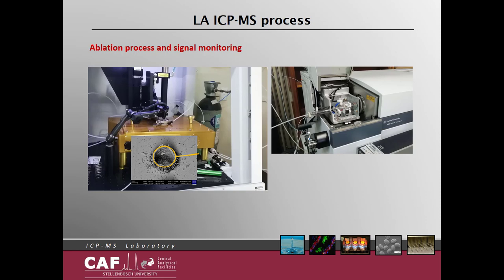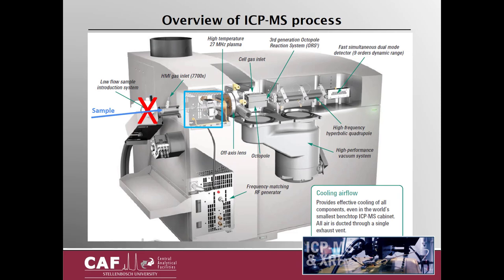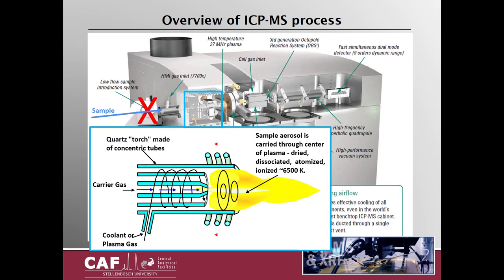Let's have a look at the ablation process. The laser beam with a set diameter of about 30 to 100 microns is focused onto the sample surface, where it volatilizes the sample material into a small dust cloud with various particle sizes from 0.5 to 50 microns. Helium gas flows through the cell and carries the sample material out and then mixes it with argon gas on its way to the ICP. The sample is then carried into the torch where argon plasma at about 6,500 Kelvin atomizes and ionizes the sample and all the elements contained in the sample material.